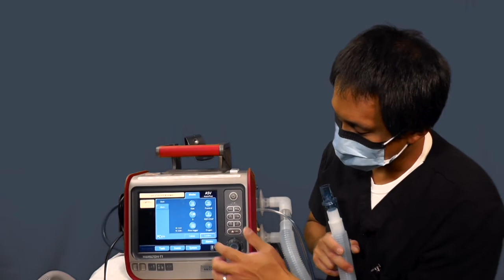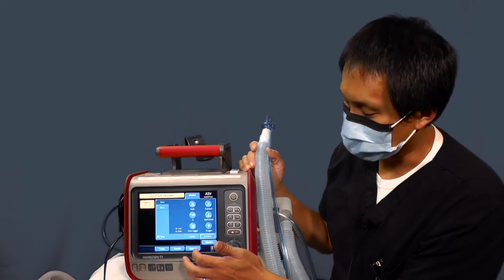Okay. And you notice it kicked me out of the screen, and that's because if you do not make changes within a certain amount of time, it thinks that it's just an accidental touch, and it will flash back to its last known settings. And in this case, it's ASV, since that was what came first when we turned the ventilator on. So it does have a timeout function.